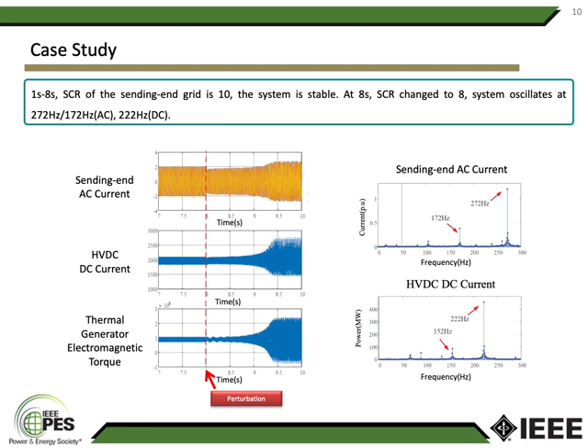To suppress oscillation, the dominant subsystem can be determined by drawing the overall system impedance curve, drawn in blue in the left figure, and the LCC-HVDC and wind farm impedance curves as well, which are plotted in dash red and dash green. At the oscillation frequency 222 Hz, the overall impedance actually depends on both the LCC-HVDC and wind farm, so these two subsystems are dominant at 222 Hz.